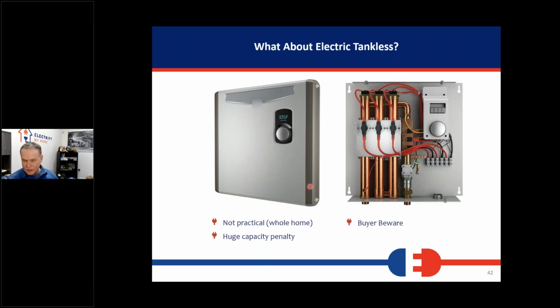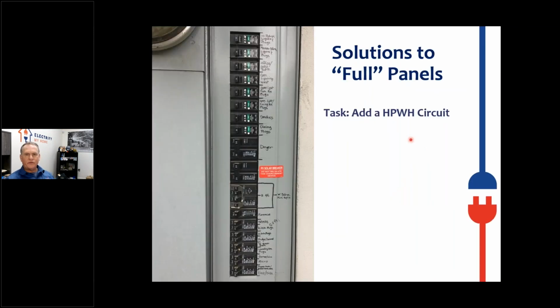Electric tankless - you can't get a big enough electric tankless water heater in California to serve a comfortable shower with cold water coming in. If you can see, this system here has 3 heaters built into it, with all these wire connections. This particular one needs 3 40-amp breakers to heat water up. If you think of how quickly it needs to heat 50-degree water up to 120, it uses a lot of power.